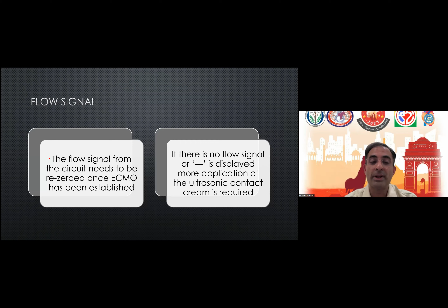At this point of time, you would also clamp the red and blue tubings, very close to the proximal reservoir bag, and await handing over of the circuit for connections. Once the priming is done and we are ensured of the smooth functioning of the ECMO console, set up the warming circuit to a temperature of about 36 degrees, and make sure that the flow signals are zeroed appropriately.